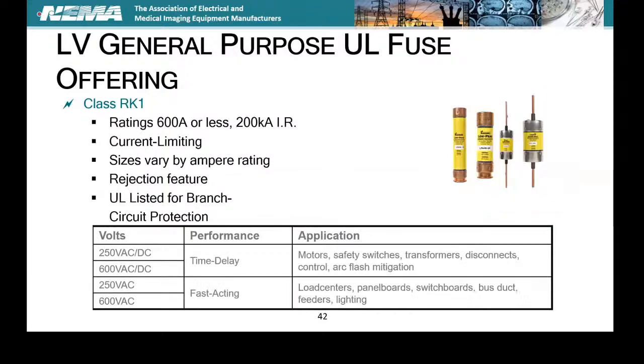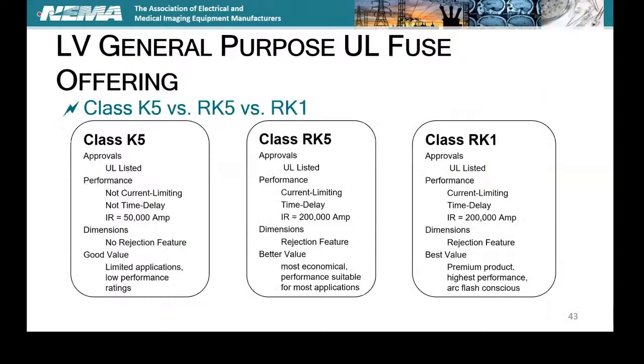But again, these are time delay fuses. And look, you can see this one here, an RK1, time delay fuse, for motors and transformers. Then you have your fast acting, that's for your feeders and your lighting and your bus duct and things of that nature. So as you move up in the power distribution system, or depending upon what your loads are, you're going to pick a time delay or a fast acting. This goes up to 600 volts, and they go up to specific amps. You've got your K5s, RK5s, RK1s.